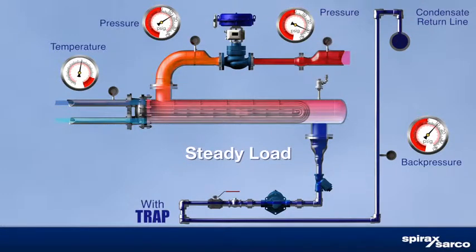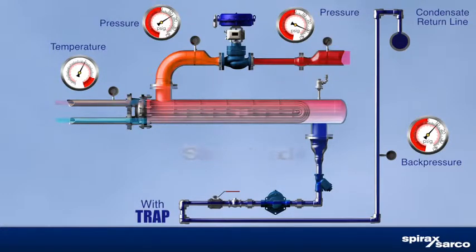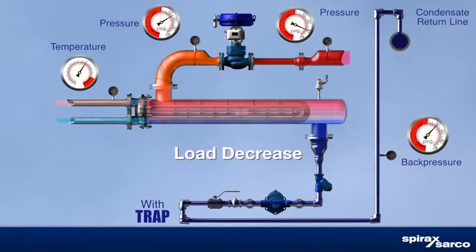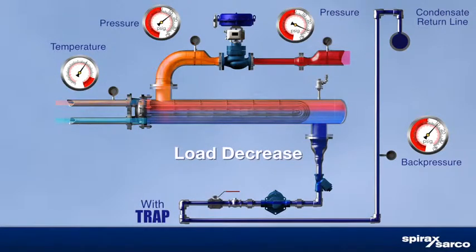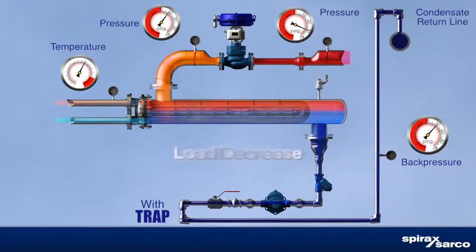Under a steady high load, differential pressure removes the condensate from the heat exchanger. Under reduced heating load, the control valve throttles down, reducing the steam pressure inside the heat exchanger. This also reduces the differential pressure across the steam trap, making the trap unable to remove the condensate.